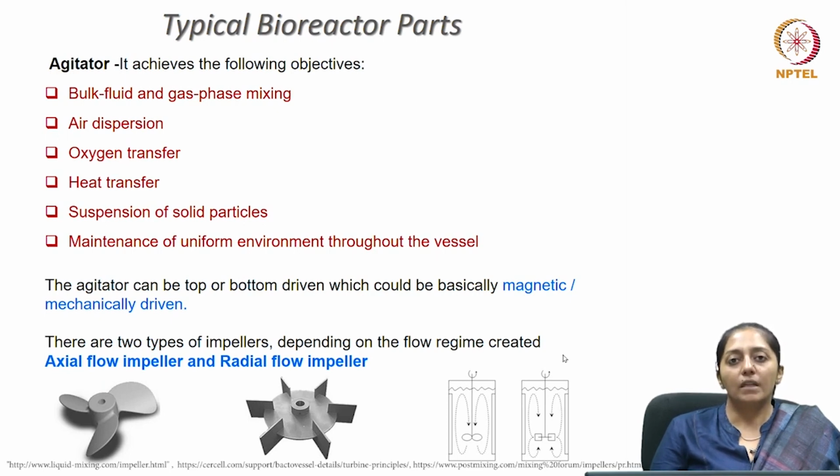Depending on the kind of flow they generate with respect to the shaft, axial impellers generate flow in the direction parallel to the shaft, and radial impellers generate flow in the direction perpendicular to the shaft, thereby creating high shear but better mixing.